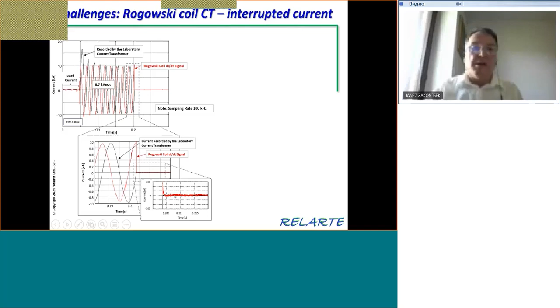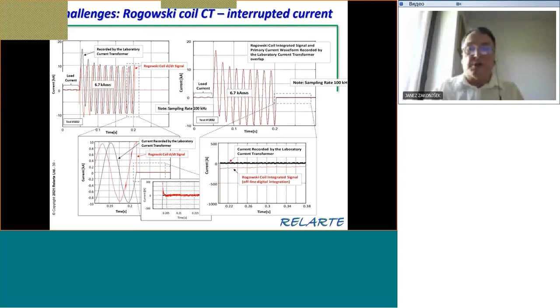Here we see the output when the primary current is interrupted to zero. Also, the di/dt goes practically immediately to zero, in a very short time. But we have to integrate this if we want to use conventional relay protection as we use it normally, so that it would be operating with this. Then the integrated current, when they interrupt the primary current, remains very high as a DC current for quite a long time. If nothing else, this can influence and initiate wrong operation of maybe breaker failure protection. So also these things should be considered when we are working with modern systems and digital substations and so on.